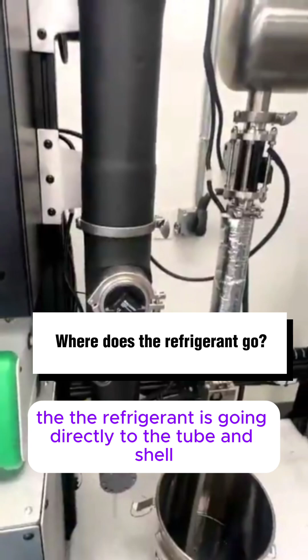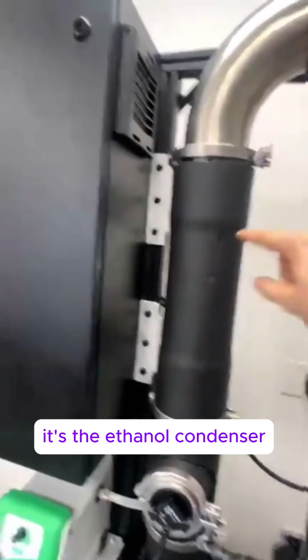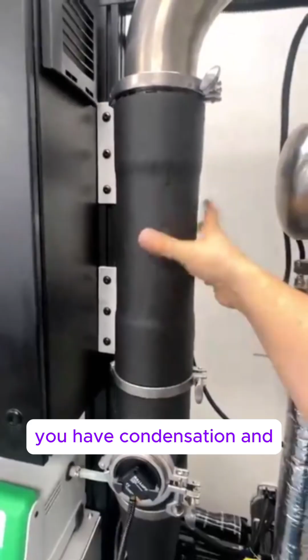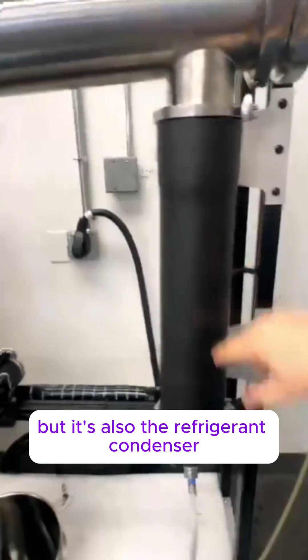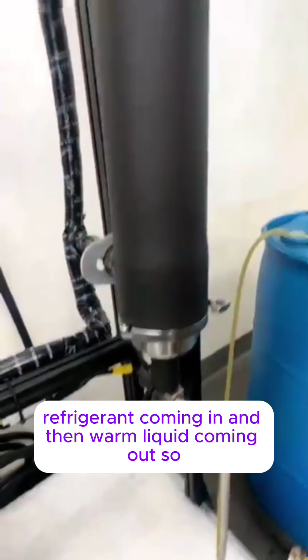The refrigerant is going directly to the tube and shell. So I keep saying that this is the condensing section. It's the ethanol condenser, but it's the refrigerant evaporator. So yeah, you have condensation and evaporation happening on both sides of this guy. And again, this is the process evaporator, but it's also the refrigerant condenser. You have hot gas refrigerant coming in and then warm liquid coming out. So it's direct contact for maximum efficiency.